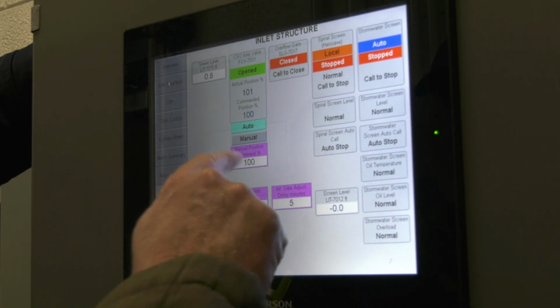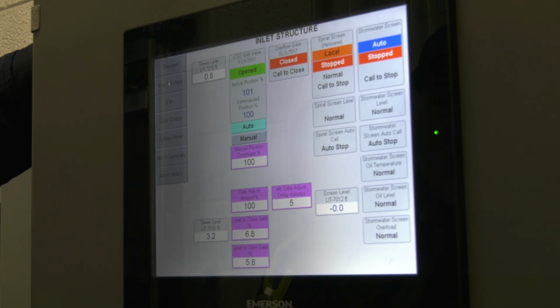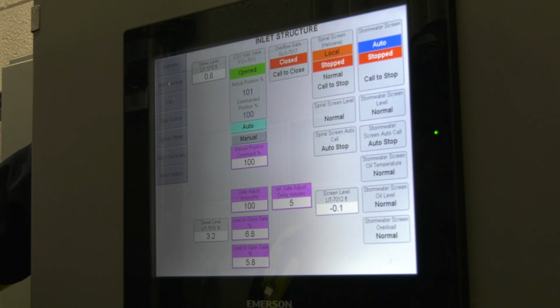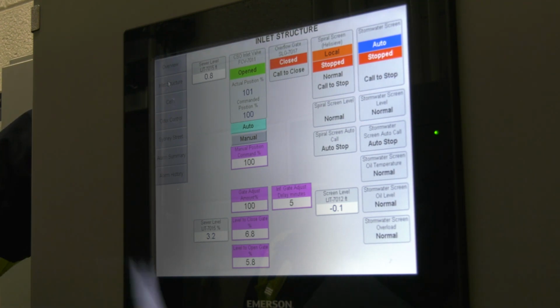Let's see, and if the Sydney Street level, LIT 7015, which you guys don't use the tag numbers, exceeds the gate closed level set point, the gate will be closed. If the Sydney Street level falls below the gate open level set point in percentages, the gate will be open.